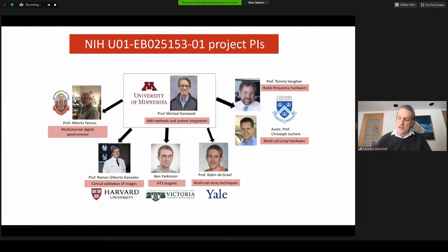In this five-year project, a multi-disciplinary team of researchers in a multi-institutional consortium have designed and are building an easily relocatable head-only 1.5 tesla scanner weighing only about 500 kilograms. The goal is to develop a radically new type of MRI scanner that will provide new capabilities for structural and functional studies of human brain and ultimately enable the diagnosis of neurological diseases in underserved populations throughout the world where MRI scanners are currently inaccessible.